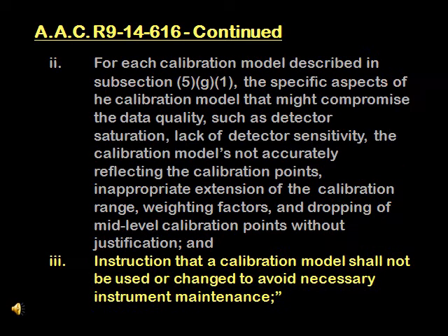And finally, Section III, that requires training on instruction that a calibration model shall not be used or changed to avoid necessary instrument maintenance. Both Section II and III will be addressed in the second part of this DVD with some other aspects important for accurate calibration of instruments.